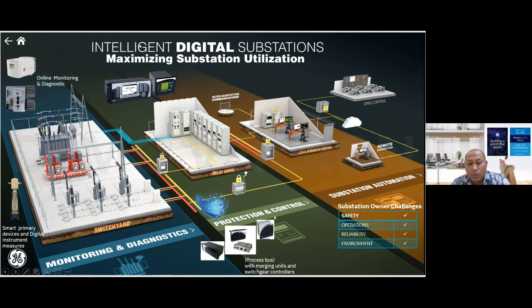And then here I would like to also show the devices inside the digital substation. We can see below here with my cursor, this is called the merging unit and switchgear controller. The function of these devices is to convert the signals from the instrument transformer outside the room into data. And this one is the protection relay, which is used for protection and control of the system. And then from the control room side, it is connected to the control room where operators can operate and monitor the system through this place, so they don't need to go to the CRP room or outside to operate and monitor the equipment. By having this kind of digital substation, it can answer the substation owner's challenges in terms of safety, operation, reliability, and also environmental issues.